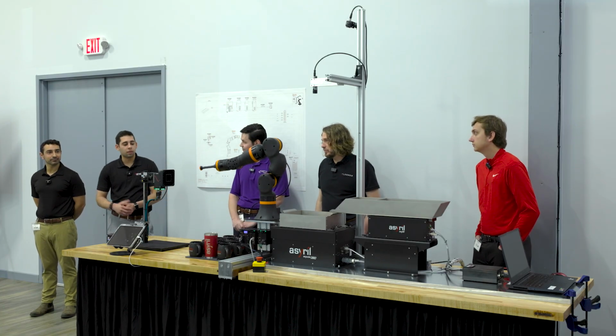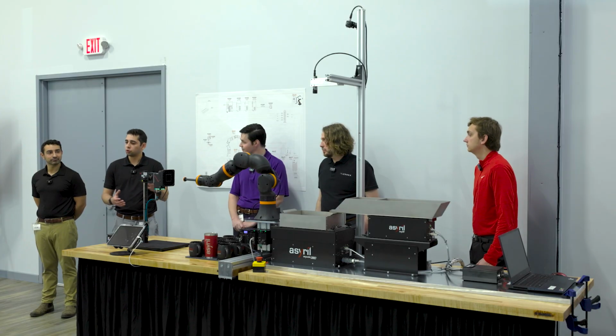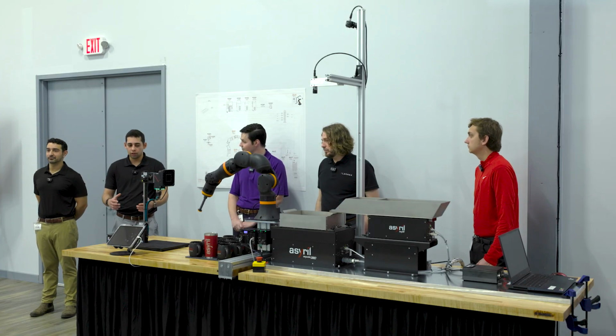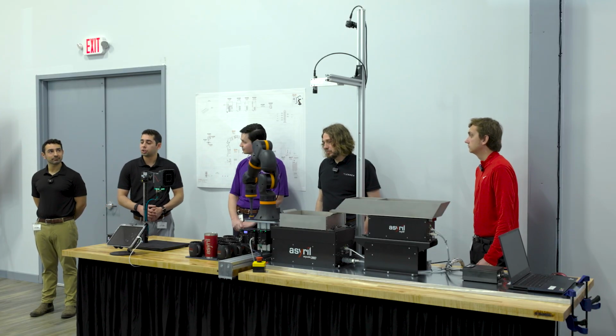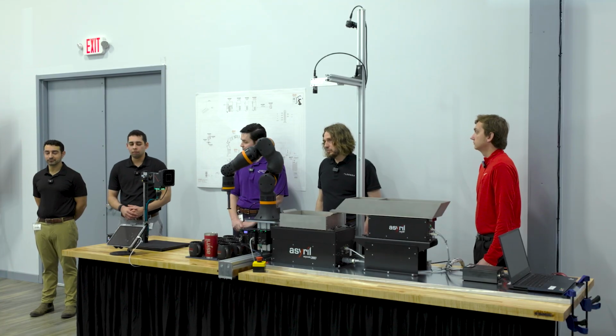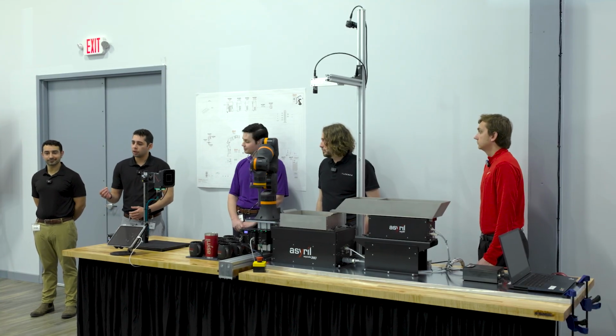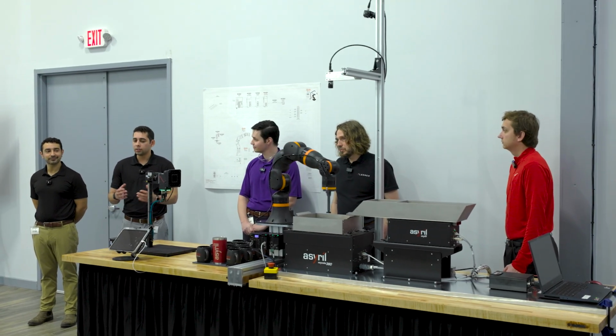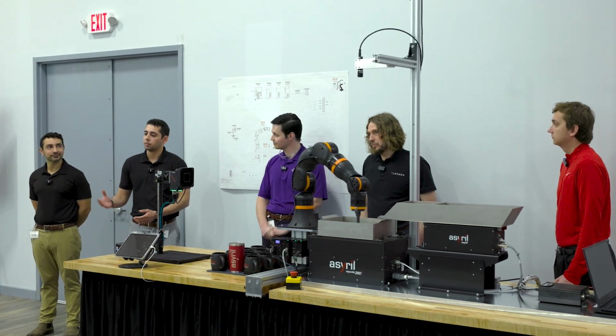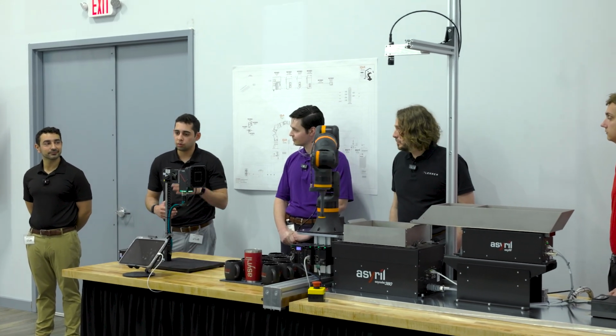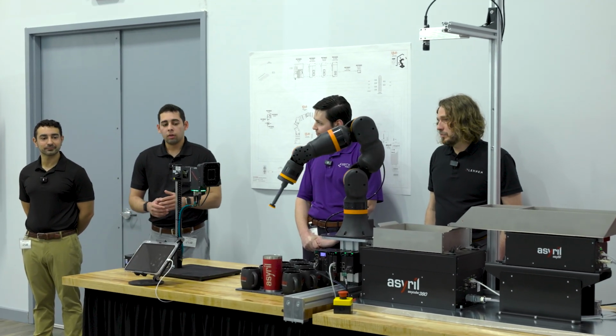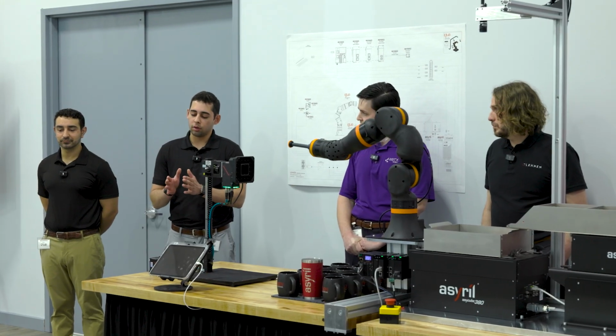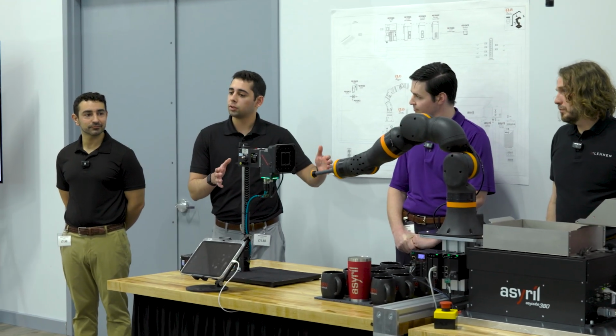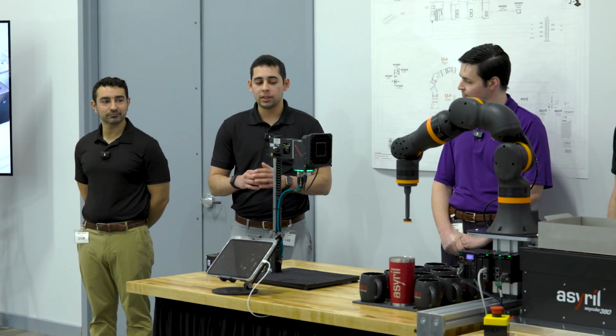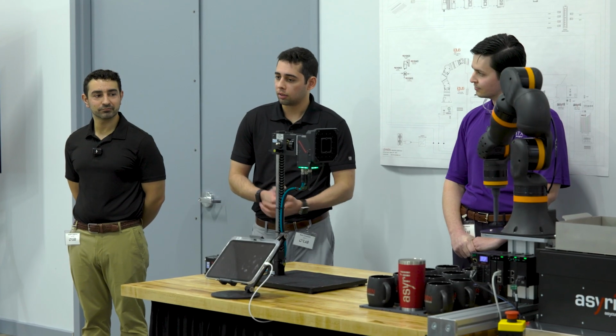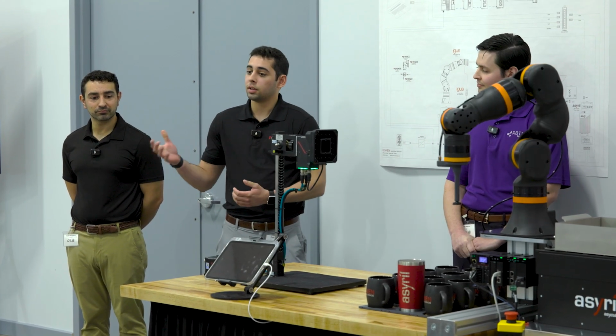It has a lot more compatibility than just your main control on a machine. Starting with the camera, we call this a machine operation recorder. You could think of it like a Ring doorbell or a dash cam in your car; essentially this camera is constantly recording your machine process. Now, when you have some sort of fault or machine issue, we have a trigger that will say, okay, we want to record up to 10 minutes backwards before that fault happened, and it's synchronized into all the ladder logic. So I'm seeing any bits turning on and off.